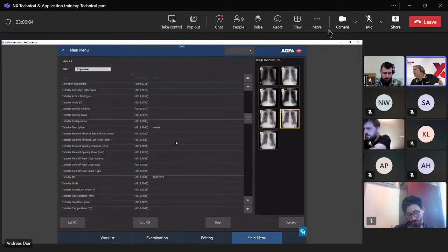It would also be possible in CR10 and CR12, but it is a commercial decision that needle IPs are only foreseen for CR15. CR35, CR85, and also CR30 cannot deal with needle IPs. We will later also see that needle IPs have an irregularity in sensitivity.